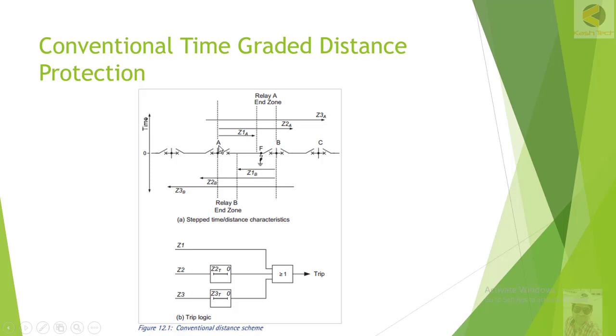The breaker at Station A will trip in Zone 2, which is 250 to 400 milliseconds depending on system protection settings. I have seen mostly 300 to 350 milliseconds used. In this case, the breaker at Station B opens immediately, while the breaker at Station A trips with a time delay. The disadvantage is that the fault will be fed by the system unnecessarily for, say, 300 milliseconds.